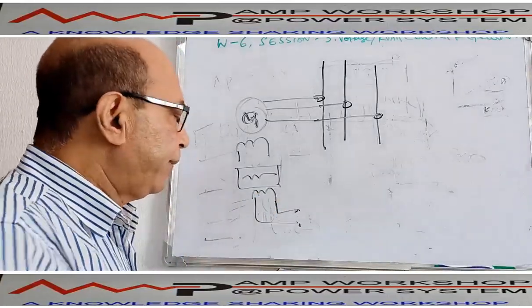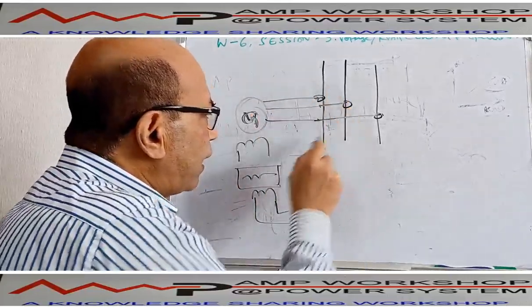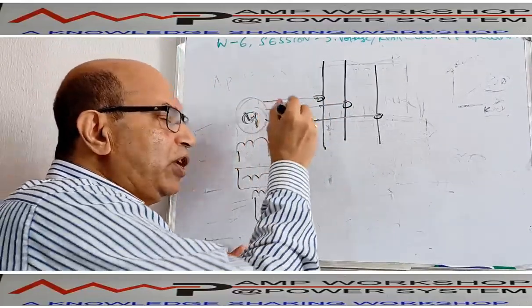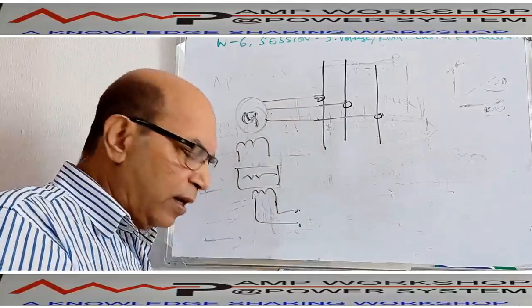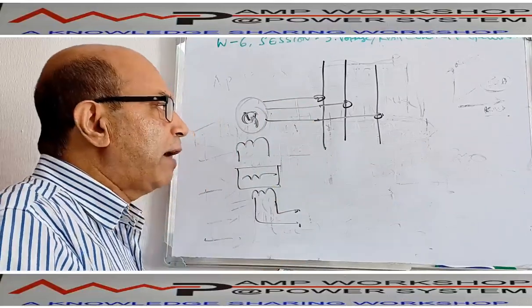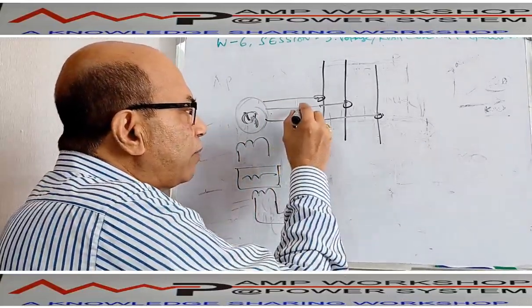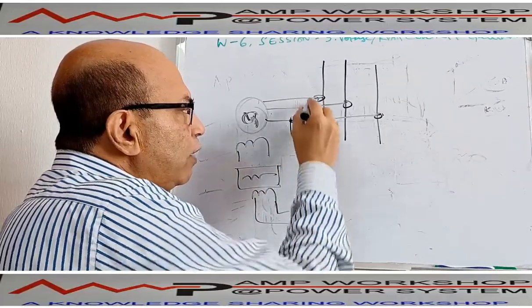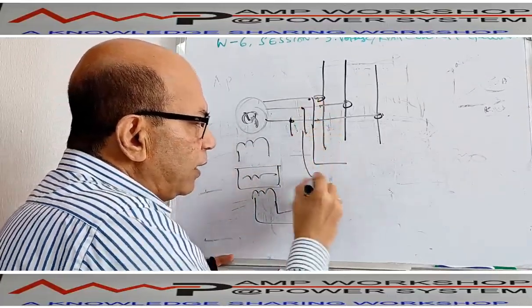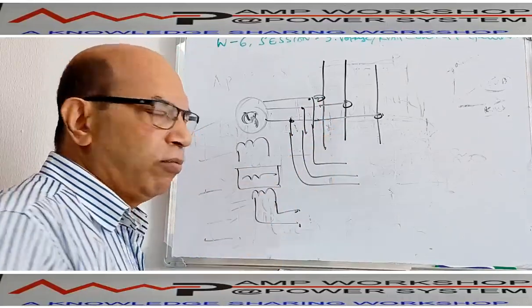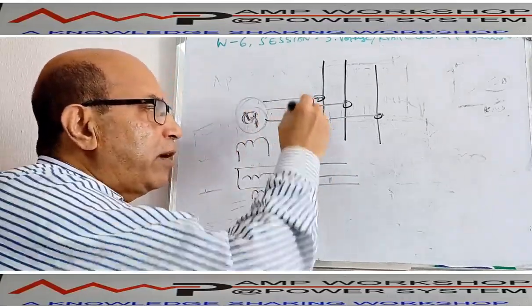So ultimately we have to control this field winding voltage. That is the requirement. If we want to control this generator voltage, first we have to monitor what voltage it is producing. How will we monitor the voltage? We will sense the output voltage of the generator. From here we take this voltage as the actual voltage. But if it is a high voltage generator, we cannot tap directly.